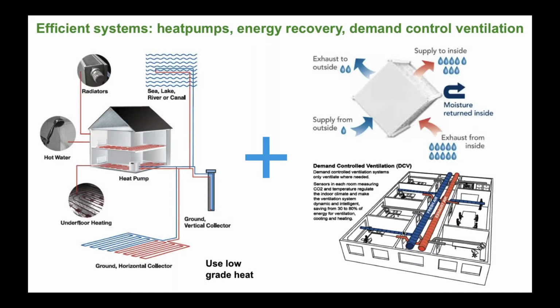But what I think is important is that we seem to constantly end up using electrically based heat pump systems that use low grade heat. That means we're supplying chilled water and hot water out to our zone level distribution systems closer to the ambient temperature, whether that's nearby groundwater or the outdoor air. That allows the heat pump to operate very efficiently because it has to do less work to generate that heating or chilled water. We're also seeing a lot of benefits from using energy recovery on the ventilation side.